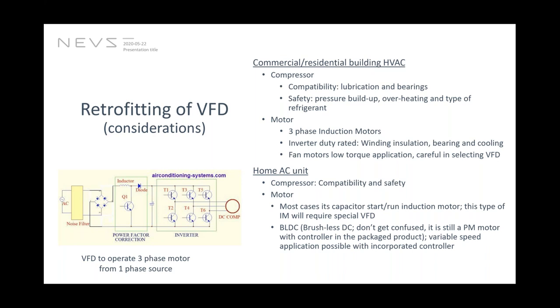Another interesting fact was the type of refrigerant. We have to be careful when trying to implement the VFD. Even if your compressor is safe for pressure buildup and overheating, the refrigerant might cause overheating at higher speeds. So we have to be careful with regard to the refrigerant type as well.